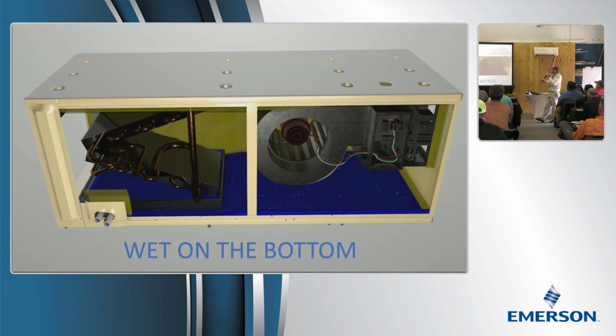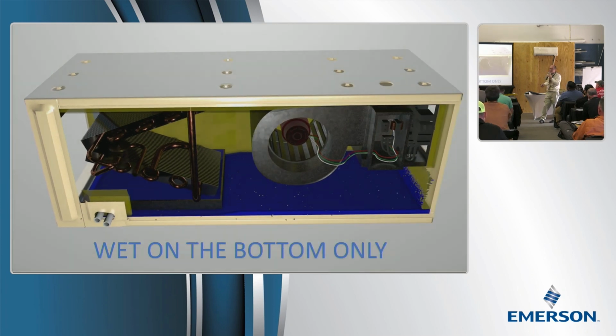If it's wet on the bottom, you should suspect the entire thing, and that's the most common thing we see: wet on the bottom of the air handler, just the bottom of it sweating. Sometimes you have a cracked drain pan, sometimes you have a clogged drain line, but after you solve whatever got the insulation wet, what we do a lot of times, how many of you like to just tear that out and throw it away? Just tear it out and throw it away once it's been wet like that.